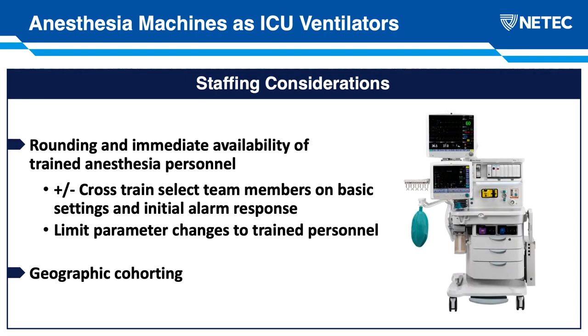And then lastly, in just thinking through how one might stand this up, we know that most facilities where anesthesia machines are present have some number of anesthesia personnel available. And in almost every instance where this has been described, there's been either continuous attendance by an anesthesia personnel or a rounding schedule that's been set up whereby an anesthesia personnel makes rounds on all of the anesthesia machines being used as an ICU ventilator at a fixed schedule, and they maintain immediate availability in the case of alarm.